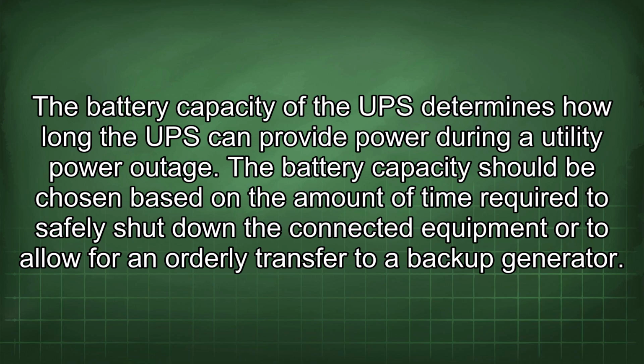The battery capacity of the UPS determines how long the UPS can provide power during a utility power outage. The battery capacity should be chosen based on the amount of time required to safely shut down the connected equipment or to allow for an orderly transfer to a backup generator.